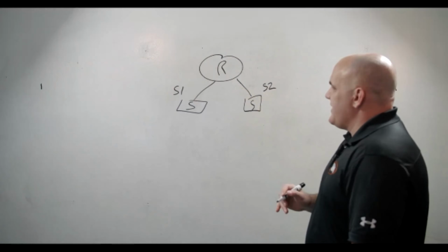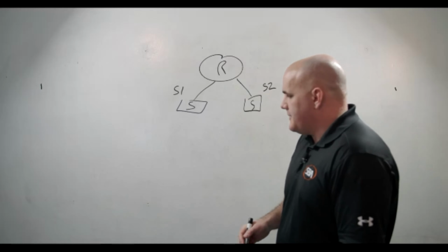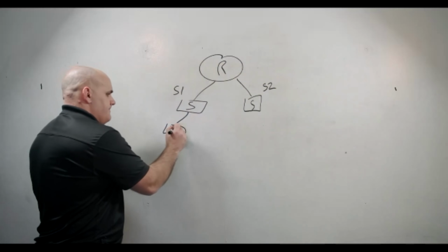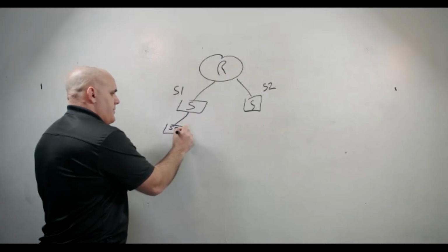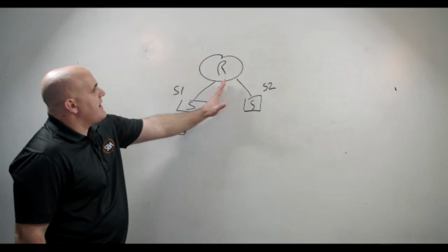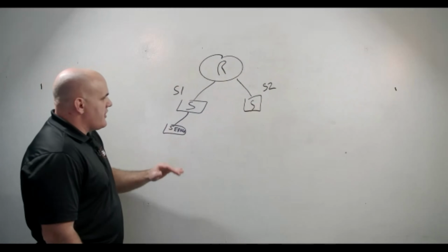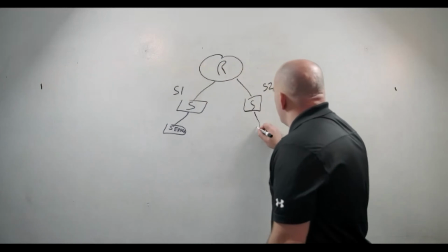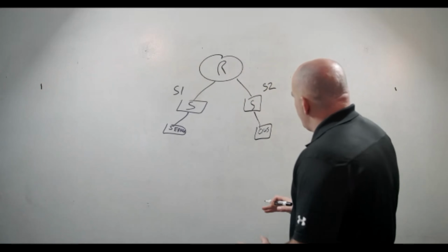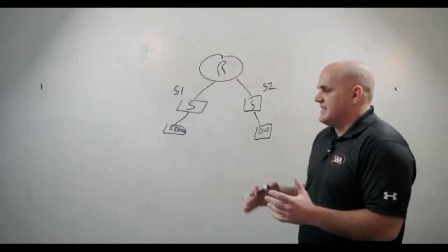And on this subnet, let's say we go to a job site. And the customer is saying, hey, I got the BAS server here. I love this example because it touches so many different things. All right. So we've got a router here. We've got a switch, subnet 1, subnet 2, the server. And then over here is the operator workstation. And so they say to us, we can't operate the server, or we can't access the server anymore.